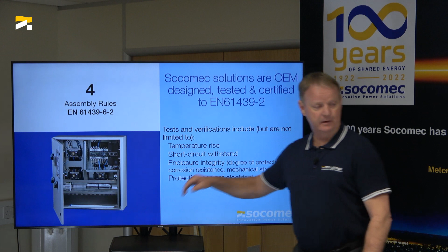These are just some of the tests. This really is a test done when everything's together, you can't do it in isolation. It has to be done when everything's connected, because you've got cables, or bus bars, so it needs to be tested together. Temperature rise, for example, because once you put it all together in a cabinet, the temperature goes up.